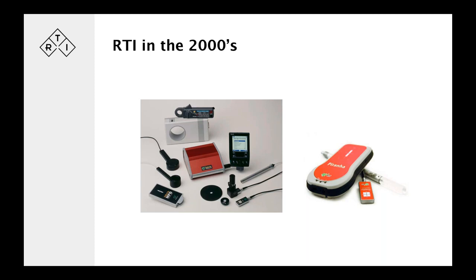That was quite successful, and we then wanted to launch a more portable and more compact instrument, and that was the Piranha, which you see to your right, a variant of the Barracuda MPD, the multi-purpose device. So with the Piranha, you could, in one exposure, capture kV, dose rate, HVL, total filtration, and of course exposure time for radiography. To that, there are possibilities to attach different probes, and we'll see more of that in the future.